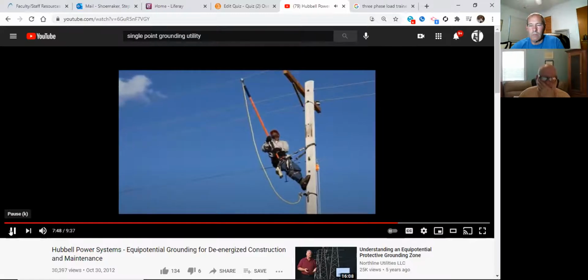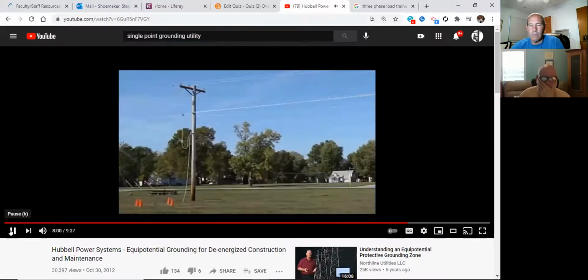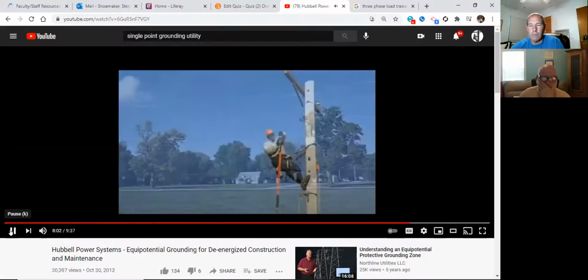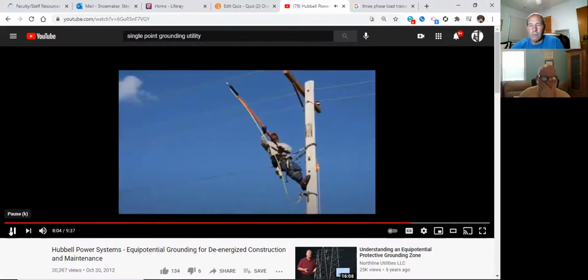It begins with the pole, which must be considered conductive itself, and connects from the cluster bar to one of the phase conductors. The personal ground forms a fault circuit path from the phase down the pole and thereby creates a zone of equalized potential above the cluster bar.